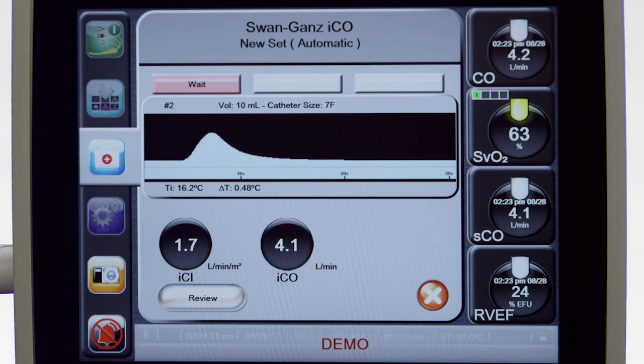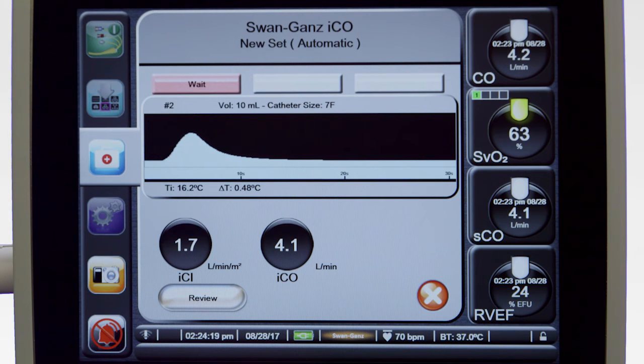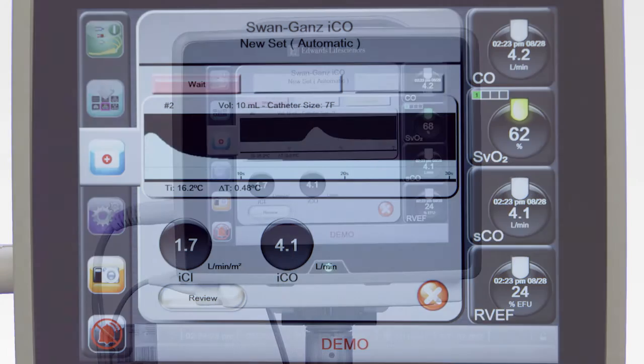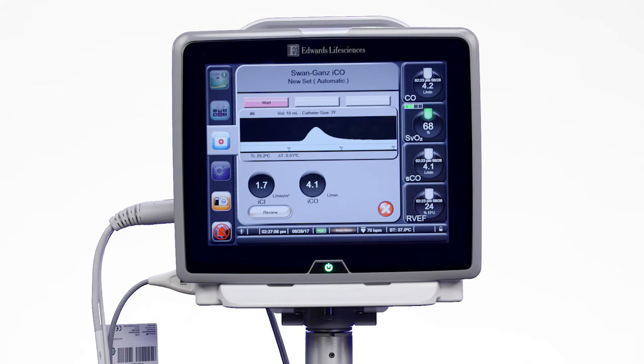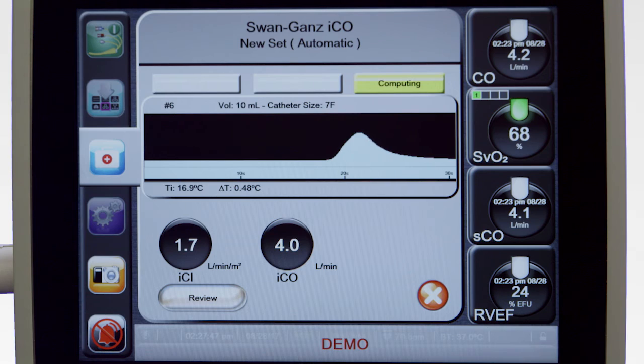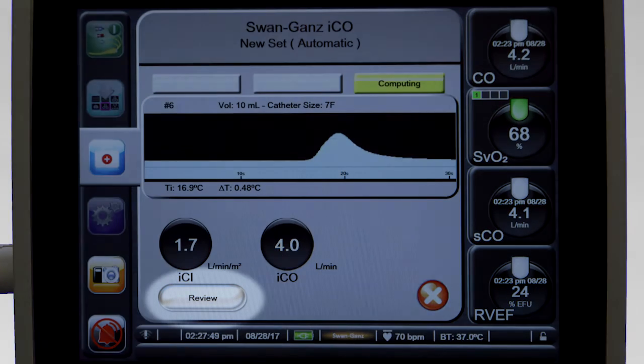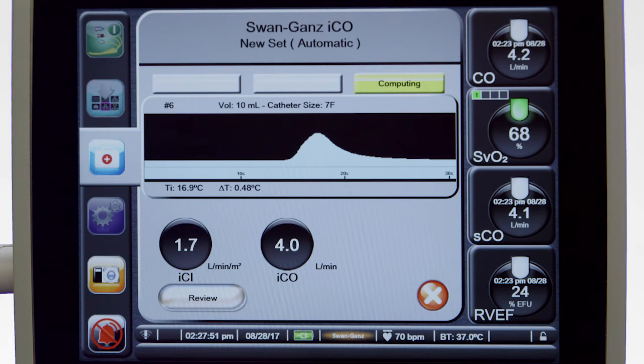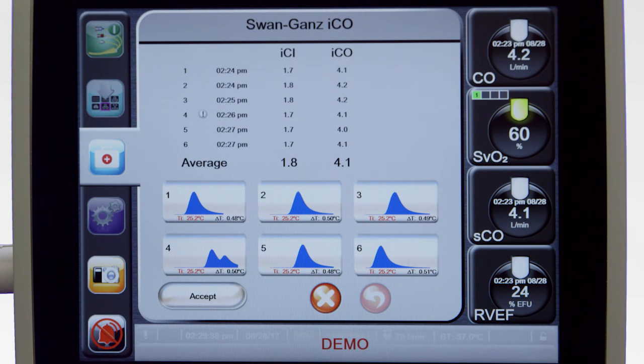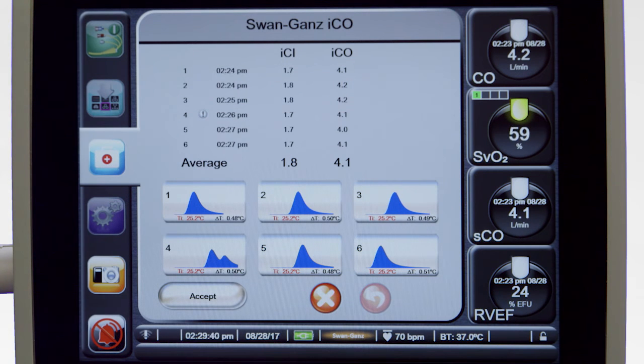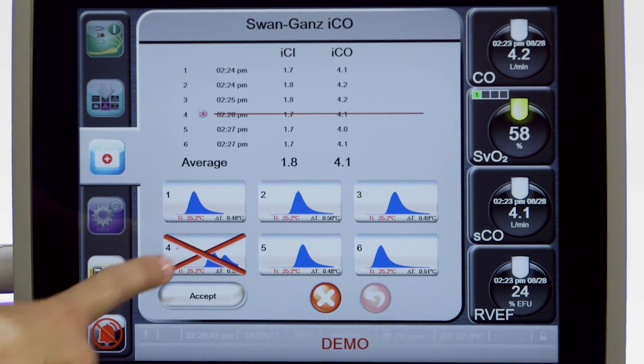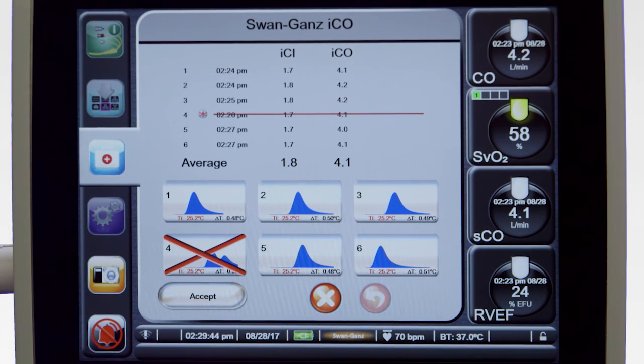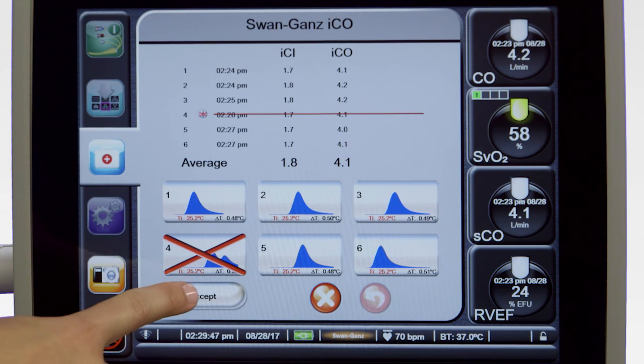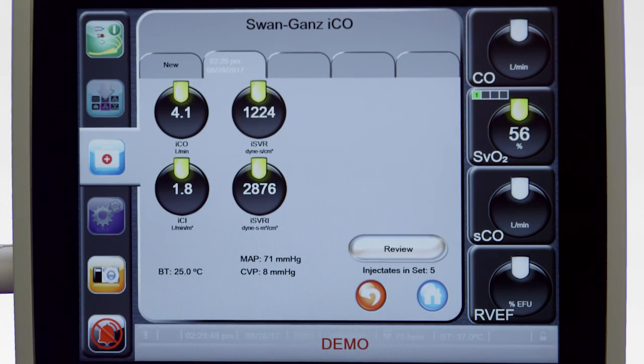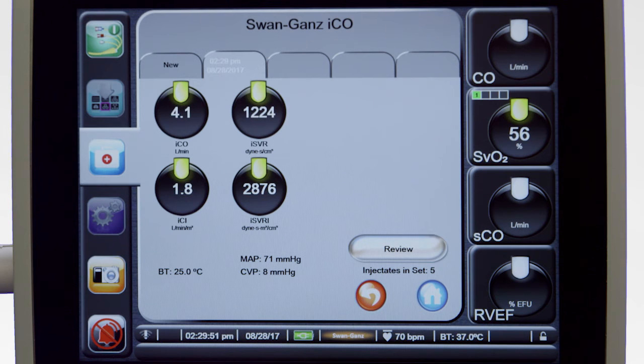The HemoSphere Advanced Monitoring Platform will automatically disregard readings for boluses deemed inadequate. After the desired number of bolus injections have been performed, review the set of washout curves by touching the Review button. Remove any reading from the final calculation by touching it on the review screen. A red X will appear over the reading, and it will not be considered in the final calculation. Touch Accept to compute the average ICO value.